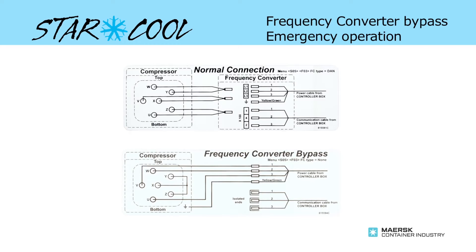Remember though, that when operating the StarCool unit in emergency mode, you no longer have the possibility to change capacity of the compressor. In other words, the unit will in this mode continuously run at approximately 60% of full capacity.